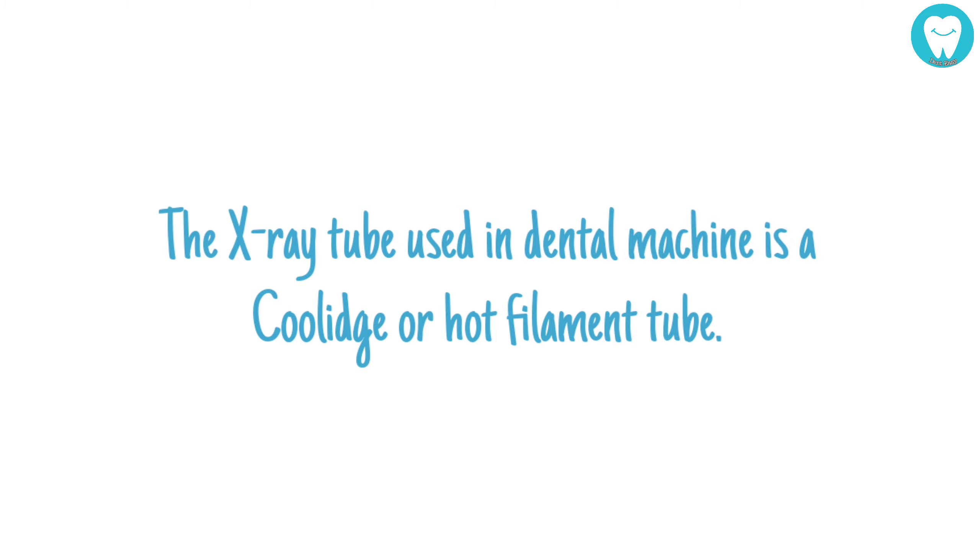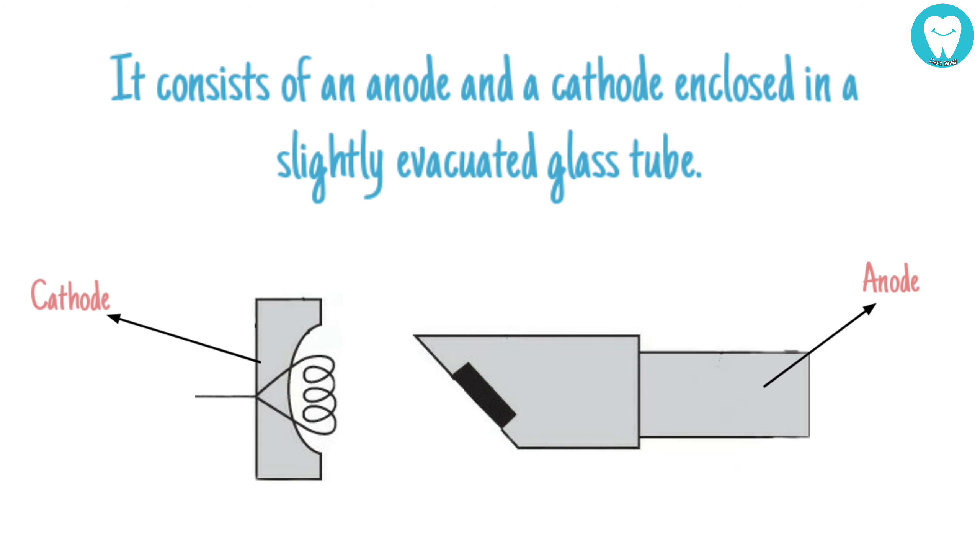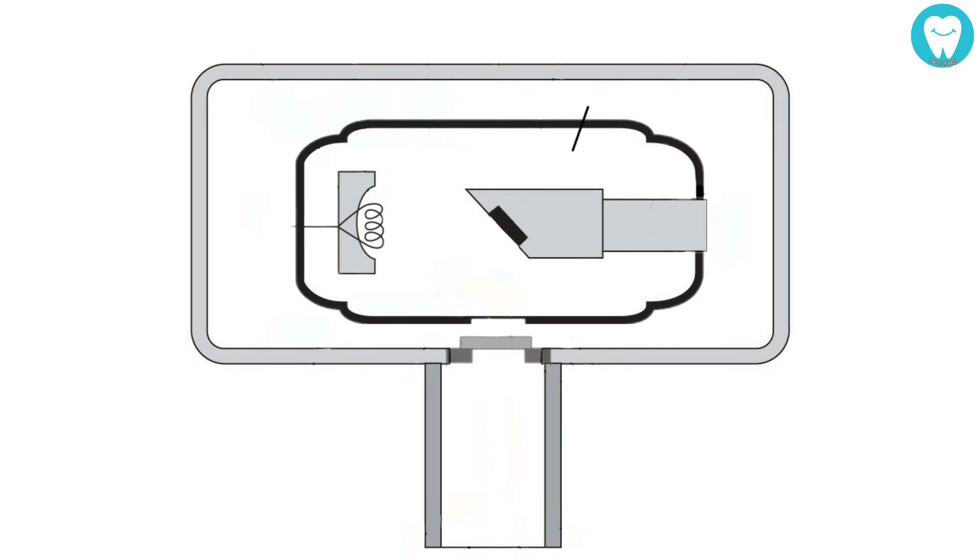The X-ray tube used in dental machines is a Coolidge or hot filament tube. It consists of an anode and a cathode enclosed in a slightly evacuated glass tube. The X-ray tube used in dentistry is approximately 15 centimeters long and 1 inch in diameter.